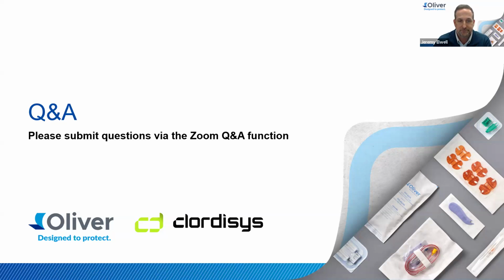Thanks. And then Emily, I know we hit on this, but I think it'd be good to just reiterate for the audience since the question popped up. Actual chamber times for chlorine dioxide versus ethylene oxide. So they can be a tenth of the time or even greater than that. A typical chlorine dioxide gas cycle from preconditioning through aeration, meaning you can handle the product right after, is generally 4 to 8 hours, sometimes shorter, sometimes longer. Longer meaning more packaging potentially or a more complex device. But an ethylene oxide cycle can be days to even a couple of weeks from start to finish in the process.